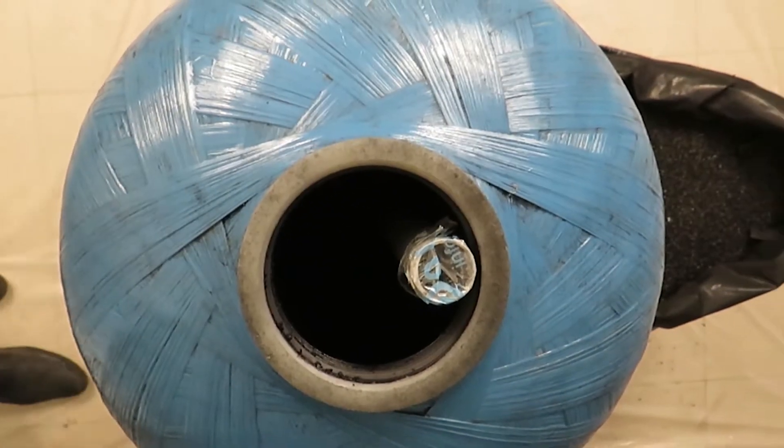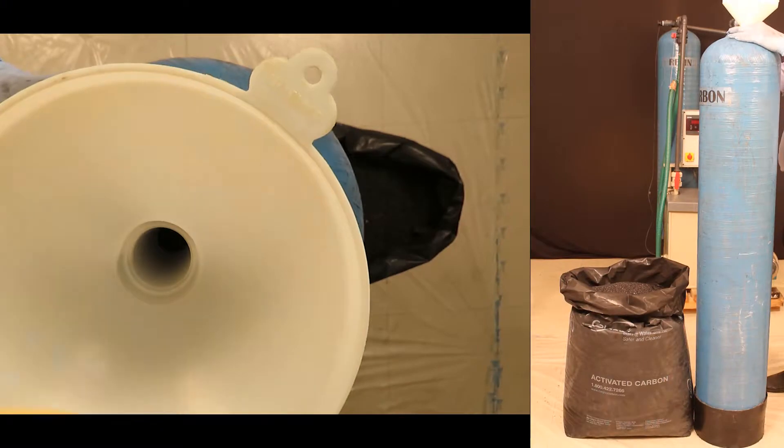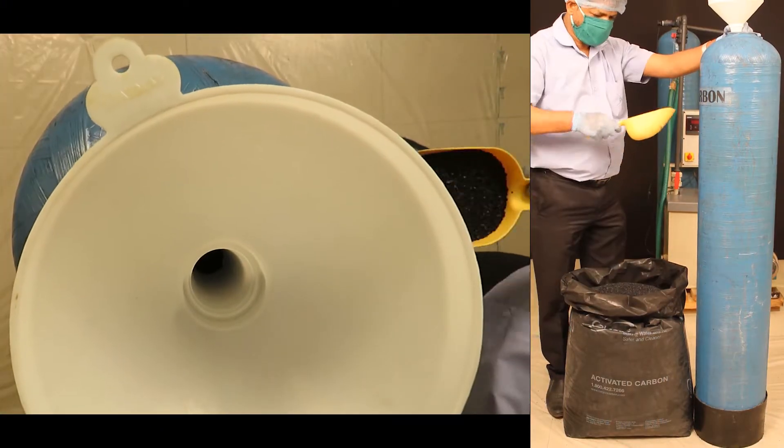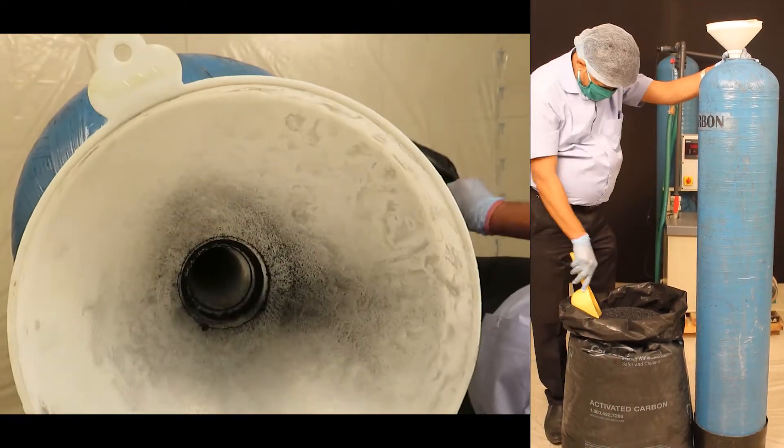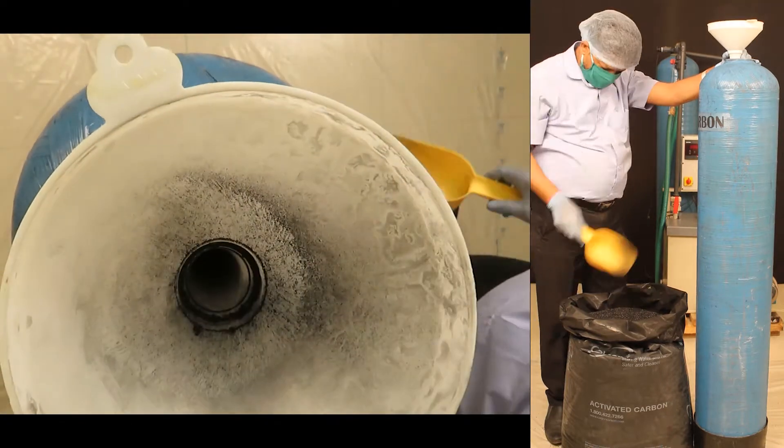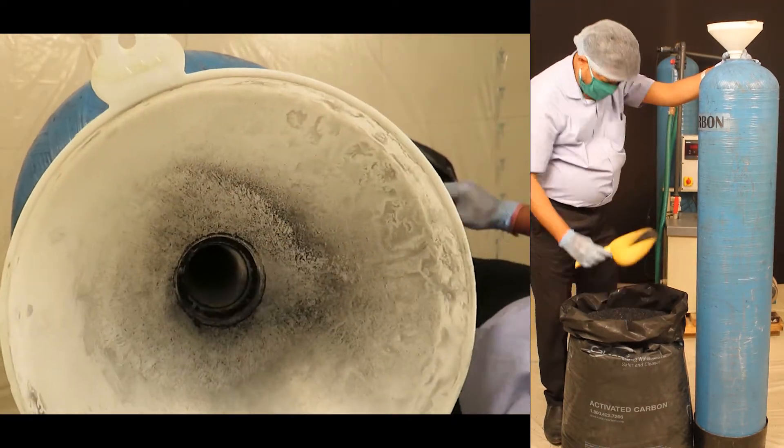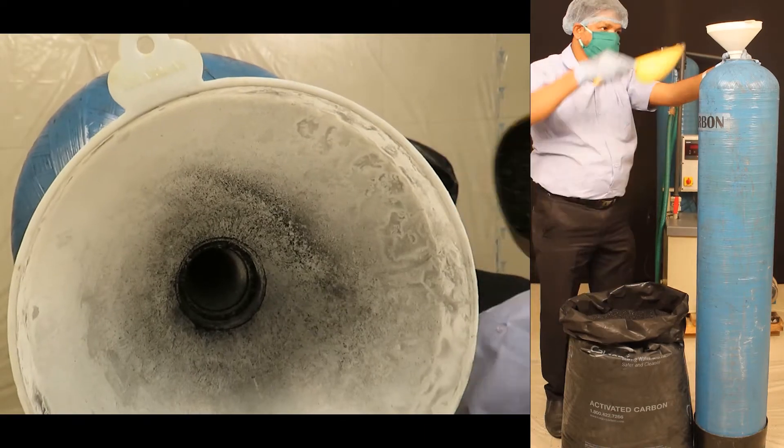Fill the new activated carbon provided by Do It Impex Private Limited into the carbon cylinder around the center pipe using a funnel or similar apparatus as shown in the video. Fill it approximately to 70 to 80 percent of the tank.